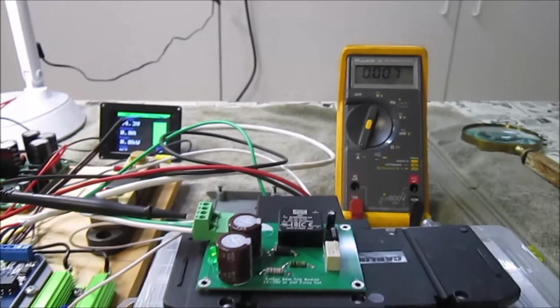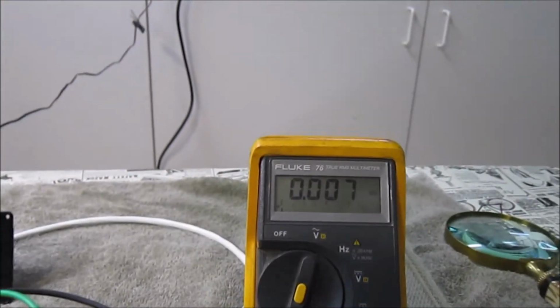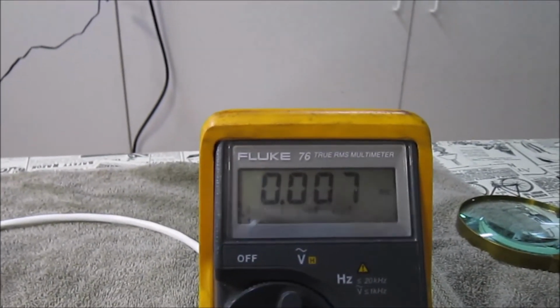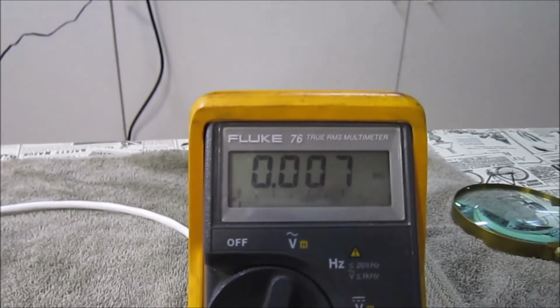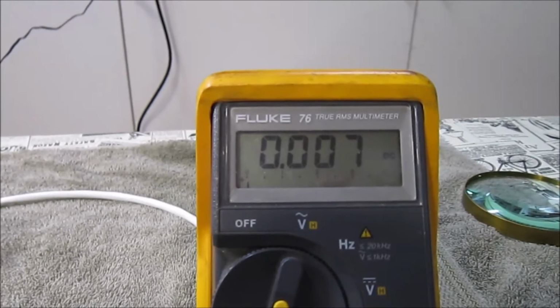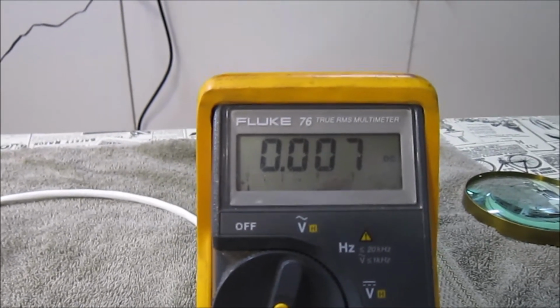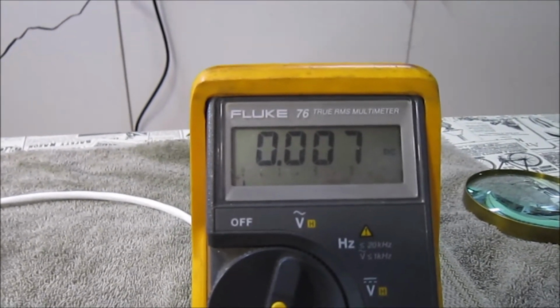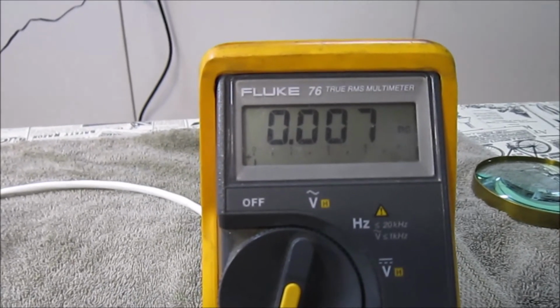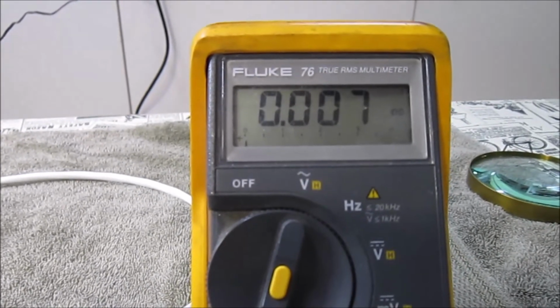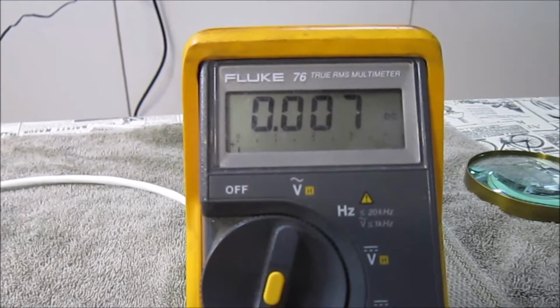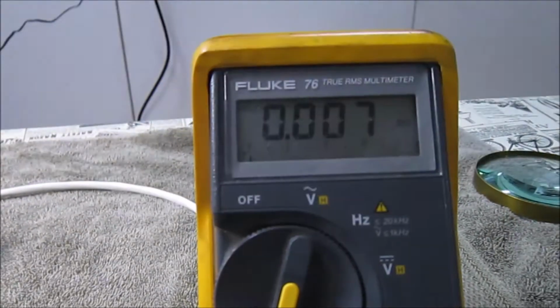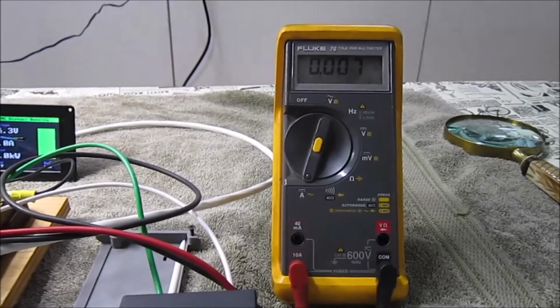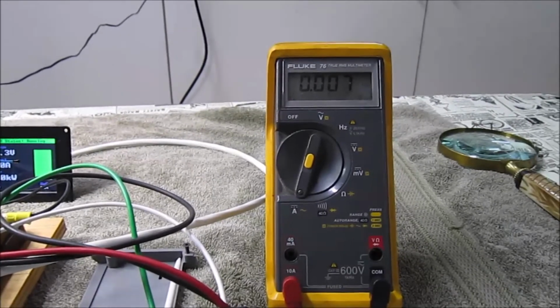And there's the standby load. So we've gone from 111 milliamps in the case of the 200 amp contactor, or 345 in the case of the 400 amp contactor, down to 7. So now you're talking about a few watt hours a month. This is definitely the way I'm going to build my next battery.